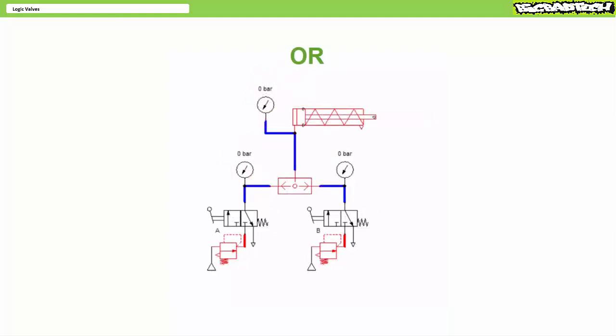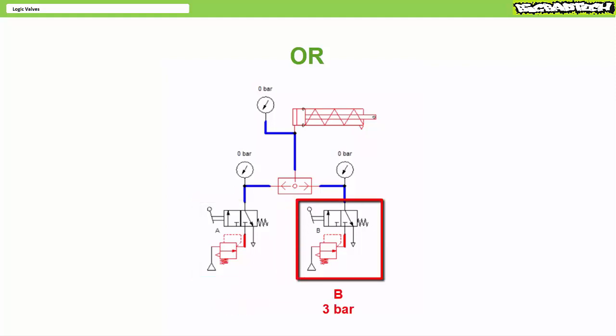Let's do the same thing for an OR valve. As previously, the regulator on the left is set to 2 bar, or roughly 29 PSI, and the valve on the left blocks or passes the signal to input A. The regulator on the right is set to 3 bar, roughly 43.5 PSI, and the valve on the right blocks or passes the signal to input B. Recall an OR valve requires a pilot signal at either input A or B for there to be an output, and when both air pilots are present it selects the highest of the two pressures.